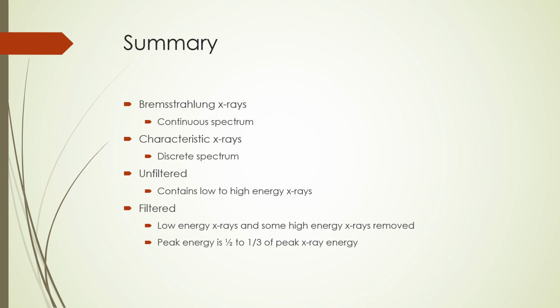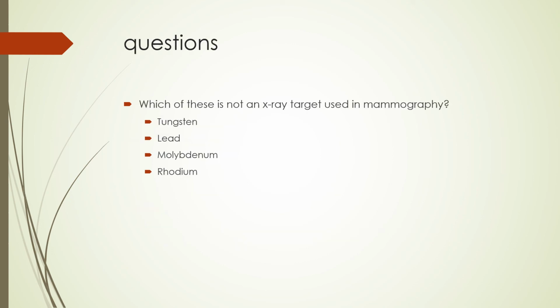Now let's finish up with a few questions. First question, which of these is not an X-ray target used in mammography? Your choices are tungsten, lead, molybdenum, rhodium. The correct choice is lead.